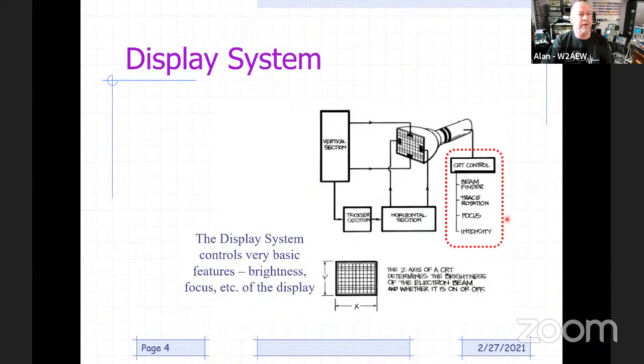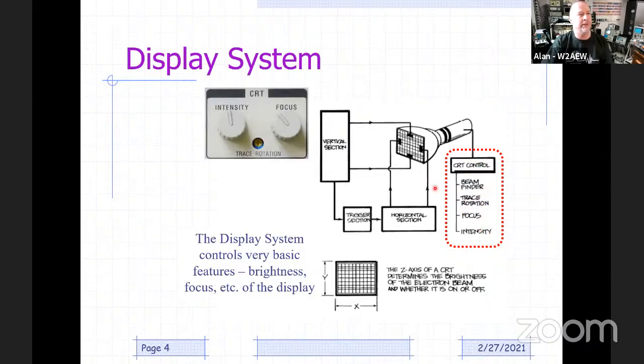So the display system, typically its controls are things like beam finder, trace rotation, focus, and intensity. And depending on the scope, they'll look a little bit different. There are some controls that we use more often, like the trace intensity or maybe the focus. Something like trace rotation, you don't use that often. Trace rotation refers to any tilt that there might be on the trace when there's no input. Ideally, it's going to be exactly parallel to the horizontal grid lines or graticule lines. But because it's a magnetic deflection system, depending on the magnetic field in your lab or where you are on your bench and where you put the scope, you might get a little tilt on the display. And this allows you to compensate for that.